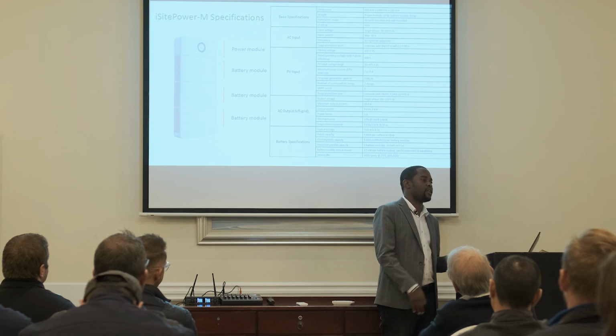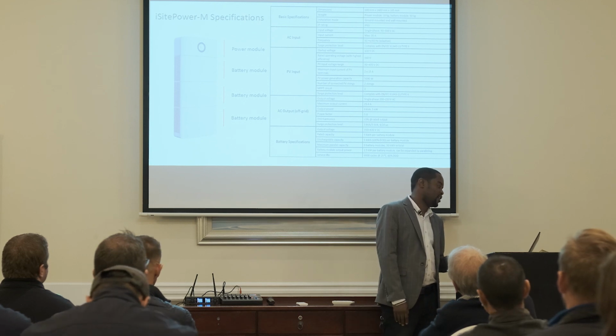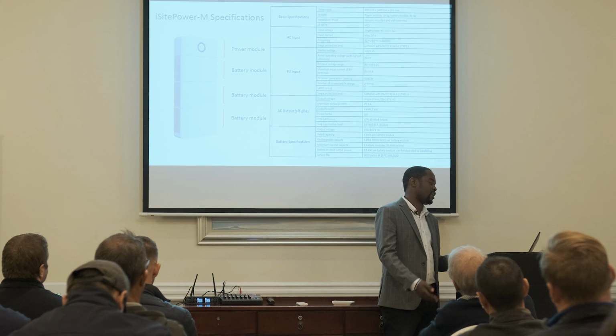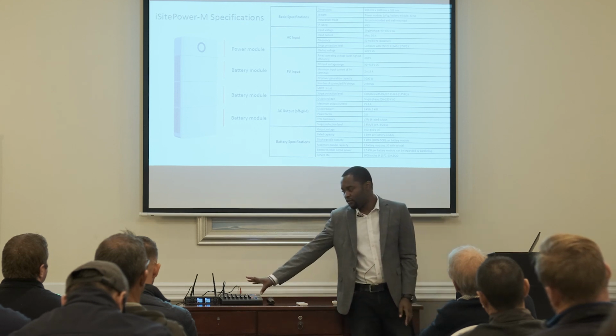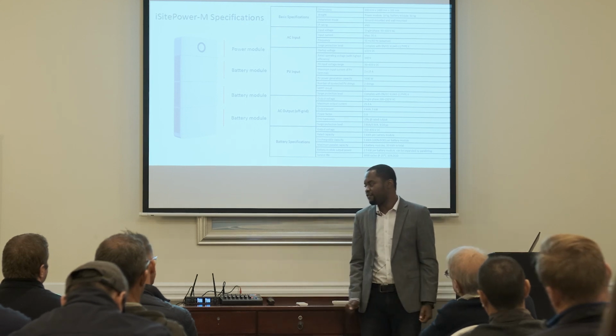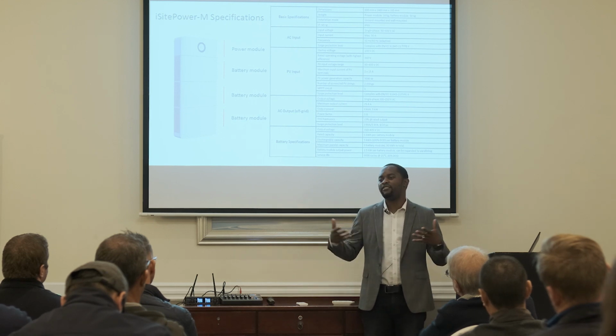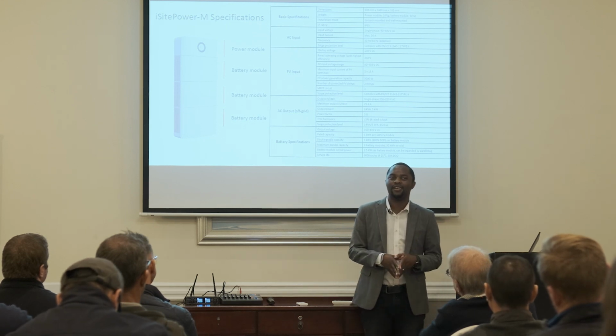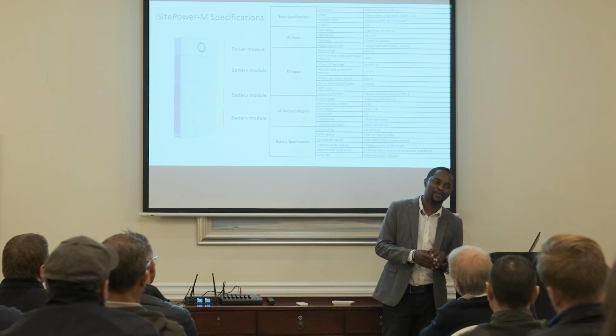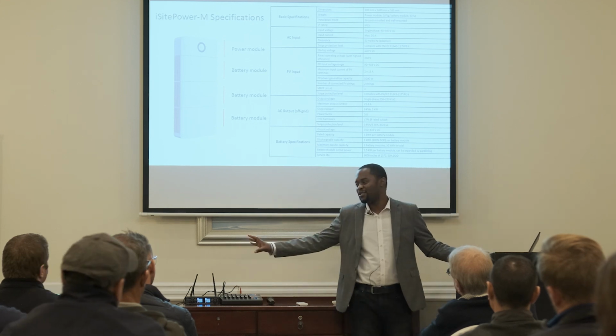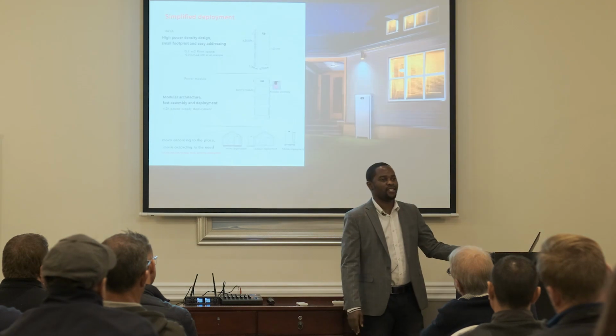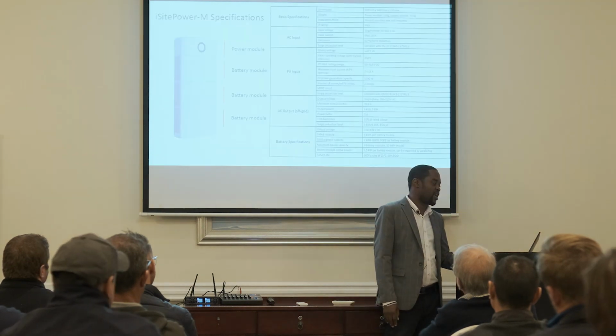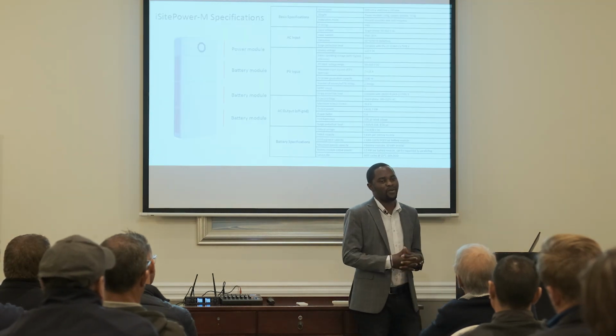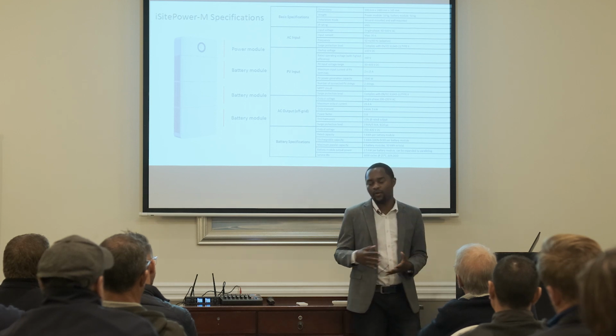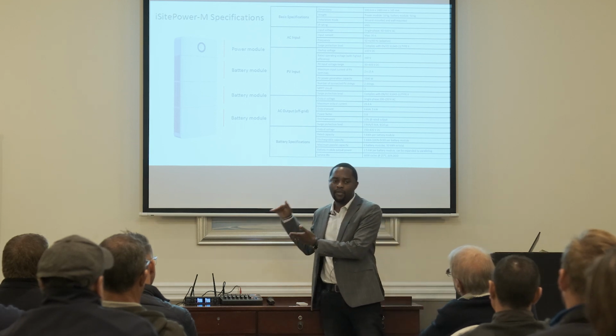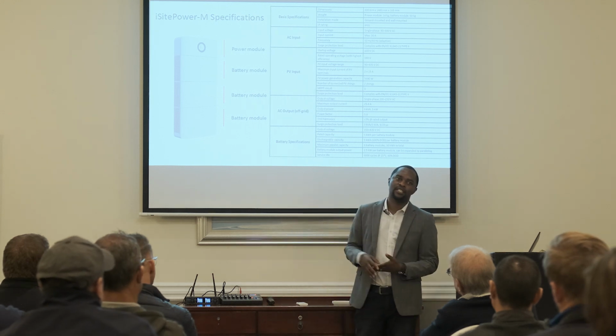Then the batteries are in parallel. You can power a maximum of 6. The voltage does not change, but now your current changes. So if you've got 1, you are limited to 2.5 kilowatt. If you've got 2, now you can have 5 kilowatt. Then if you've got 3, 7 kilowatt, 7.5. No, it can't be 7.5 because now you are limited to the size of the inverter. We had another client who was saying, oh, so I need 3 batteries so that I can have 7.5 kilowatt. Then if you want more than 5 kilowatt, you're going to buy another power module. Then you stack your batteries again.